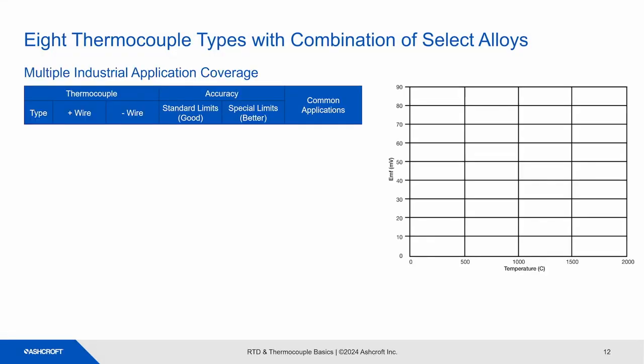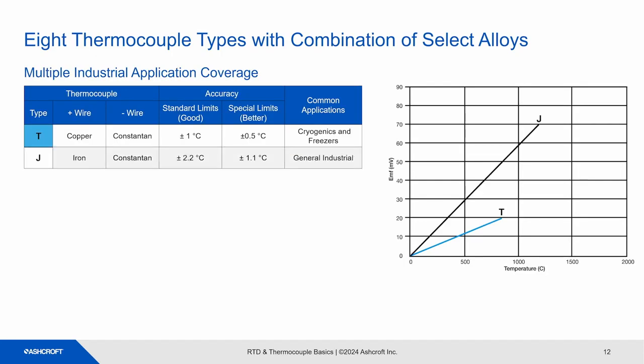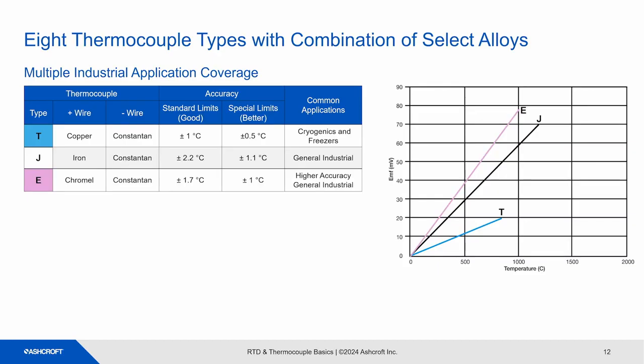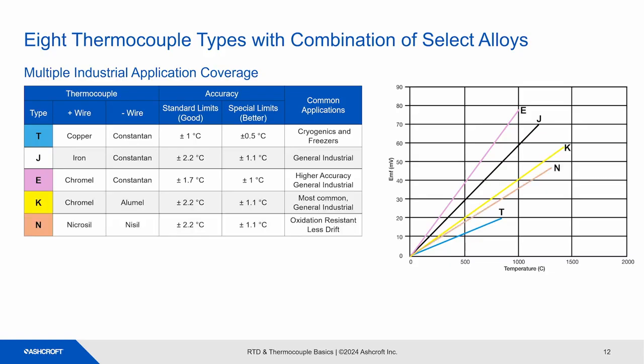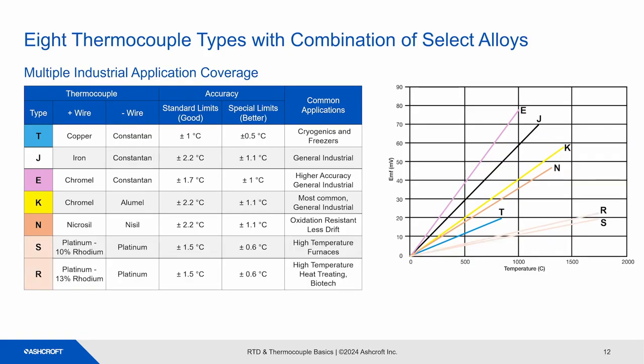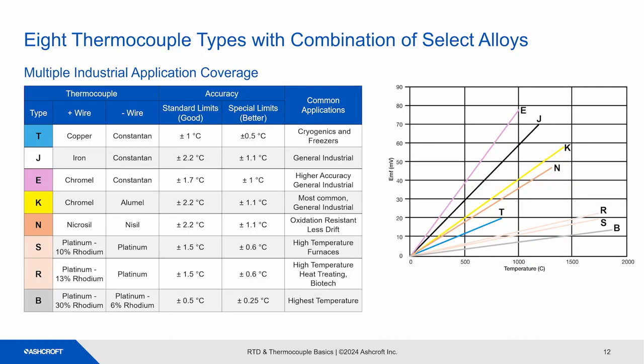There are 8 thermocouple types that are used in different applications. Type T is typically used for cryogenic and freezer applications. Type J is used in many general industrial applications. Type E is used for higher accuracy measurement. Type K is the most commonly used thermocouple for general industrial applications. Type N is used in applications that need better oxidation resistance and less drift. Type S is used for high-temperature furnaces. Type R is used for high-temperature heat treating in biotech applications. Type B is the highest temperature thermocouple. Thermocouple types vary in the usable temperature range and cost. Higher temperature ranges equal higher cost, like the S, R, and B thermocouples.